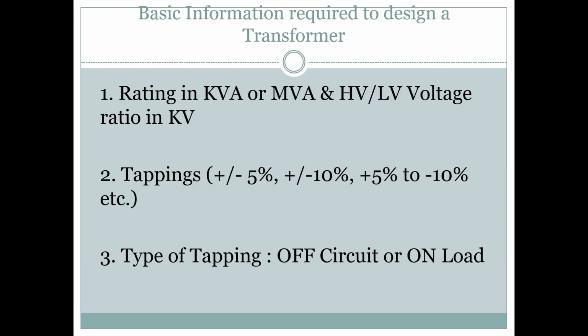I think you were telling about that residual voltage and all these things that stay there, and sir told you to take that out. So when we are doing off-load, that means I am taking the load side off. High voltage is there. It already has an induction effect, so current is already there in the LP1. At that point of time, if I want to change the tapping, it will just blast there. So that is on load. That is not allowed.